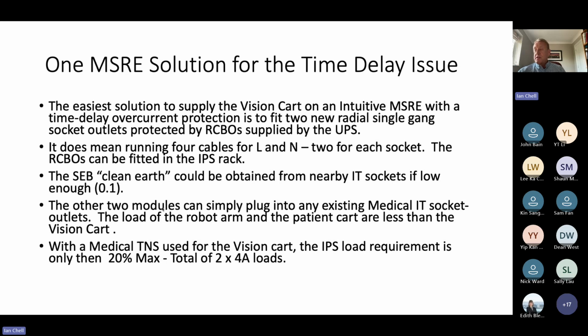So that's 2 sockets, and I'll show you a picture in a minute. These are it, and you label them vision cart only. And the reason you have two is because if the RCBO goes on one, you can plug it in the other. There's a neon on that to show whether it's live or not. That's easy to understand by the operator. And hopefully, if it goes out on the second one, they don't plug it into anything else, because that means there's a proper earth fault on that medical device. Okay.